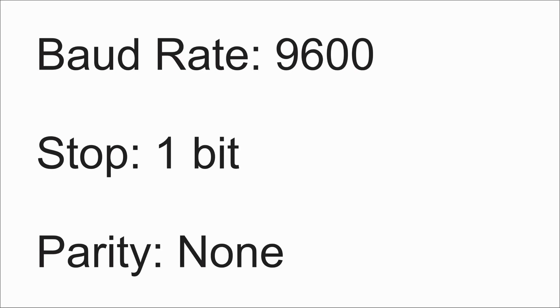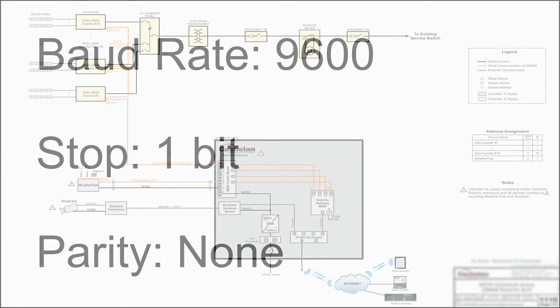To properly facilitate the communications, the inverters must have the correct baud rate, stop bit, and parity bit settings, as well as a distinct slave address for each separate inverter. For this device, baud rate is fixed to 9600, and communications are set to use one stop bit and no parity bit. These settings cannot be changed by the user.